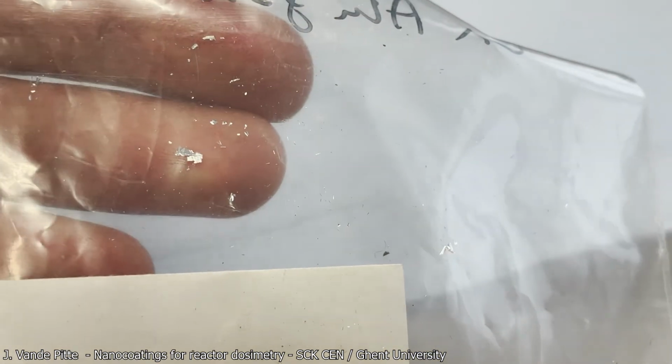We argue that when the dosimeters were punched, the metal cylinder actually damages the layer by the contact with the coating. So it is clear we have a structural problem with our coatings. In physical vapor deposition, it is common practice to add some sort of adhesion layer to relieve stresses between the coating and the carrier. Therefore, we made new coated foils and added a 5 nanometer titanium adhesion layer.